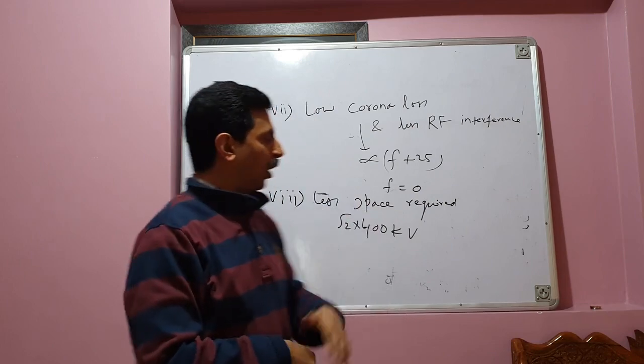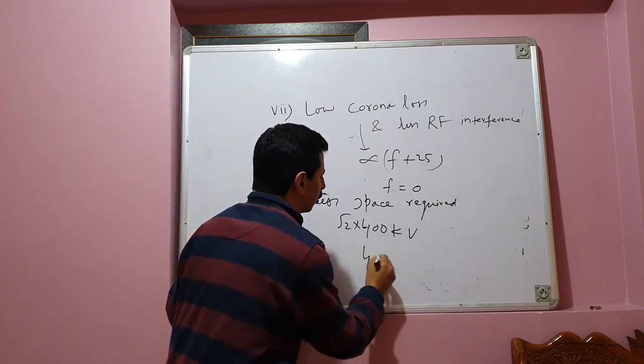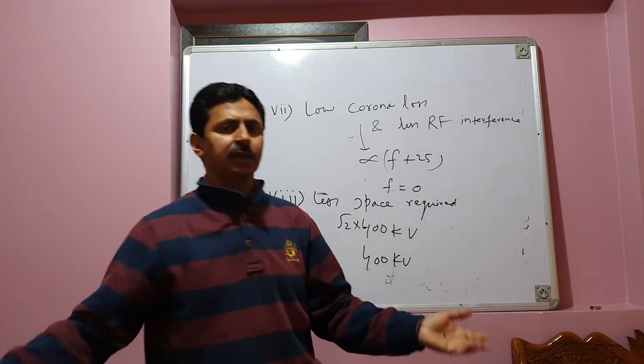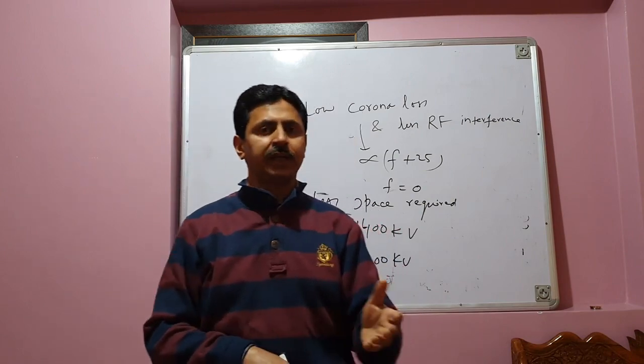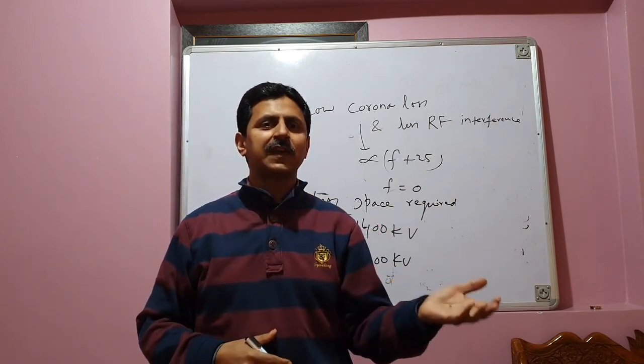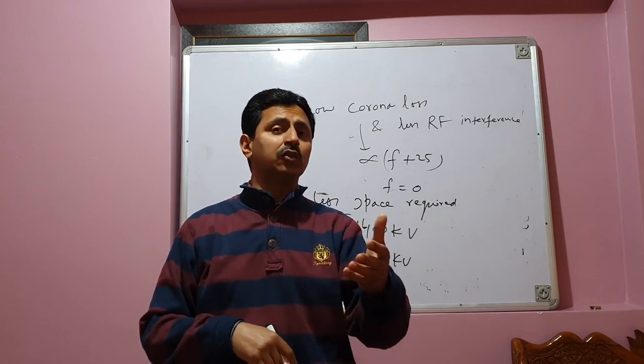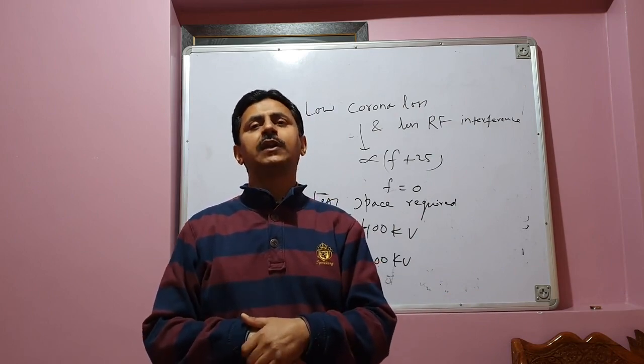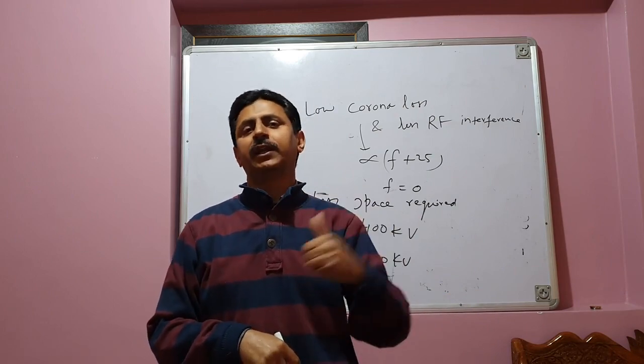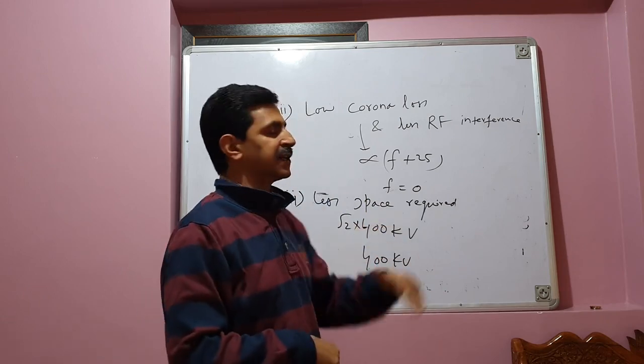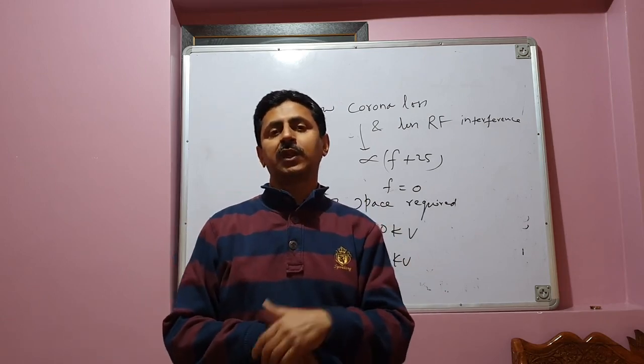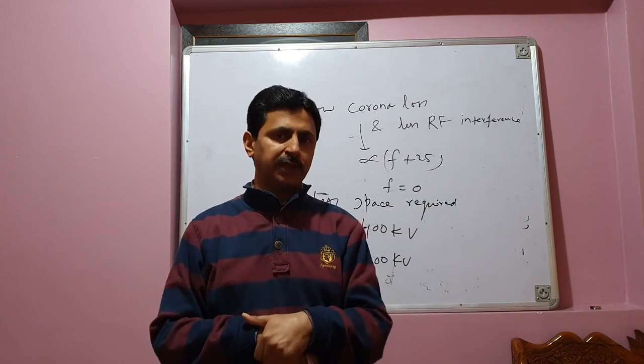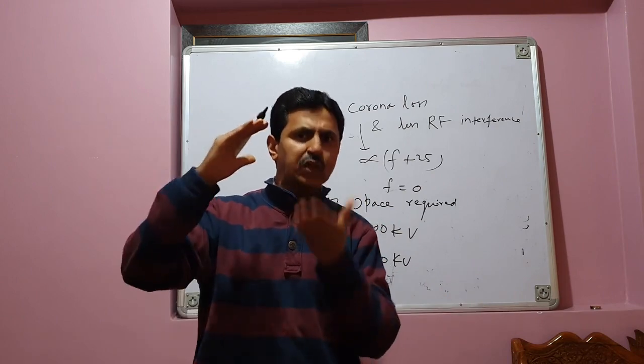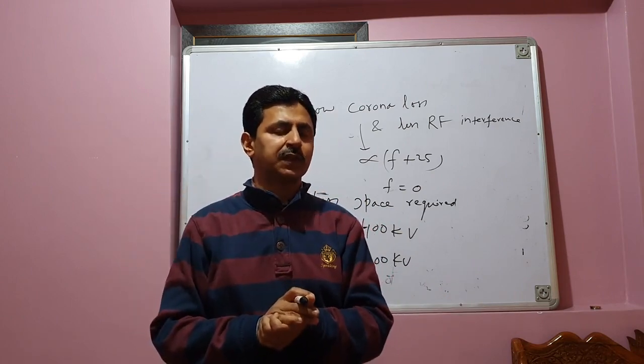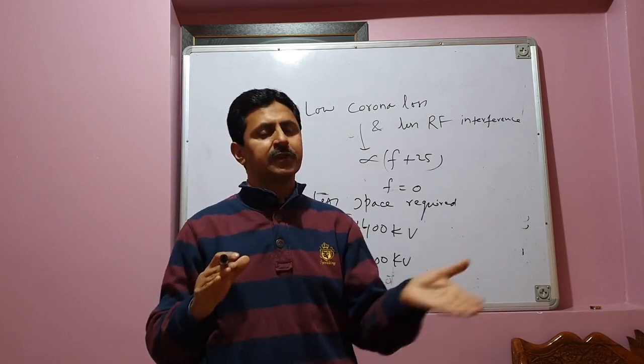On the other hand, if you are transmitting power over a DC transmission line, and again, voltage of the line is 400 kV, in this case, you don't need to multiply it by root 2. You have to design your insulator for 400 kV. Whereas for an AC transmission system, you have to design your insulator for √2 times 400 kV. So therefore, the size of insulator in HVDC transmission is less than the size of insulator in AC transmission.